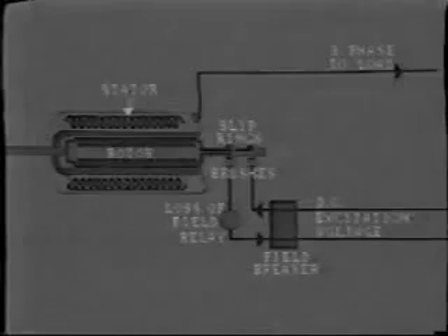However, this will probably lead to low voltage at the generator terminals, and more important, serious overheating will occur in the stator iron. If the field cannot be restored promptly, the unit should be shut down. Normally, protection relays are installed to detect reduction or loss of excitation. These relays may be used for alarm purposes, but more often they initiate tripping of the unit. Earlier loss of field relays worked by measuring current in the excitation circuit. When this fell below a preset level, the relay operated after a time delay.